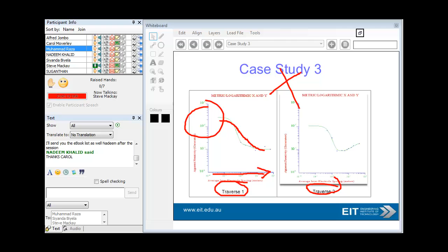So here's case study 3. You've got a water pipeline parallel to the main test, and that's interfered with the test data for the middle section. So when doing your earthing or resistivity measurements, you've got to be careful you're not close to any water pipelines which could impact your measurement. Today water pipelines are not such a big issue as they were 20 or 30 years ago, and why would that be? Because we don't use steel pipes anymore, we use good old PVC, so that doesn't have a problem.